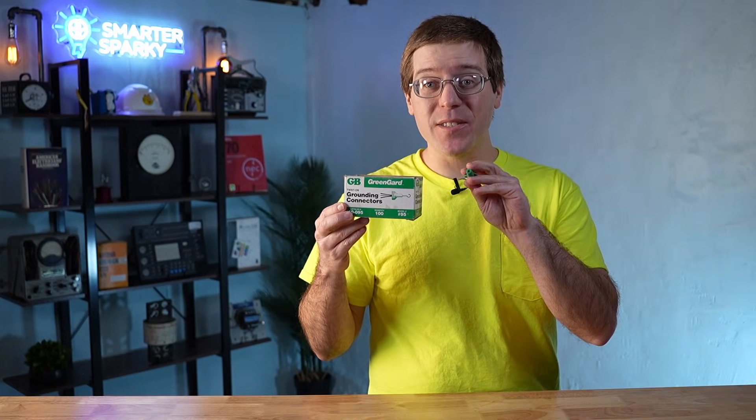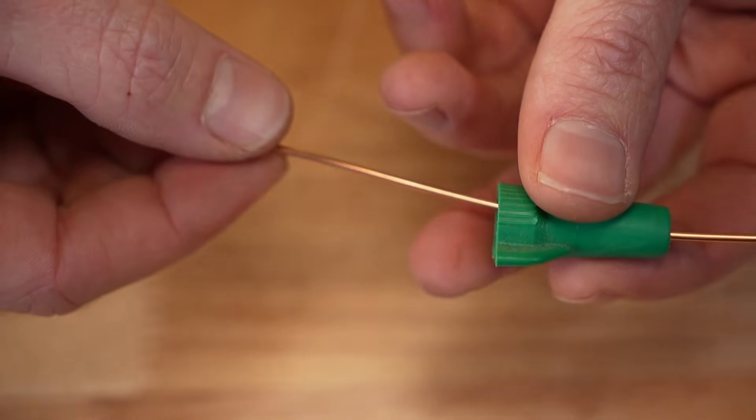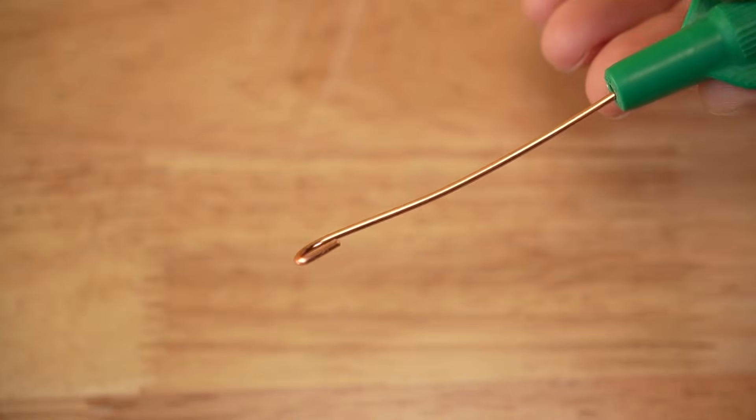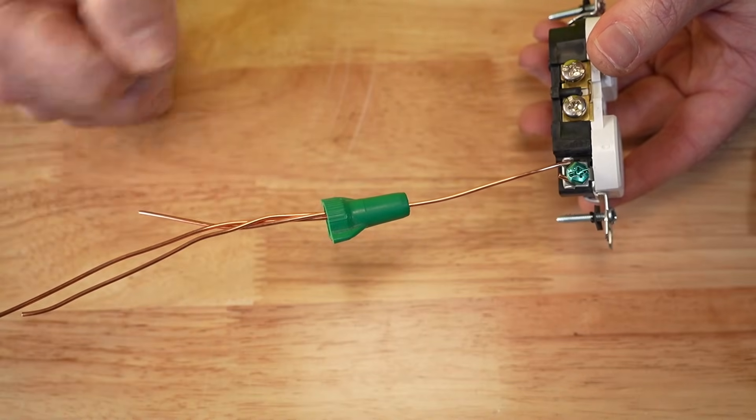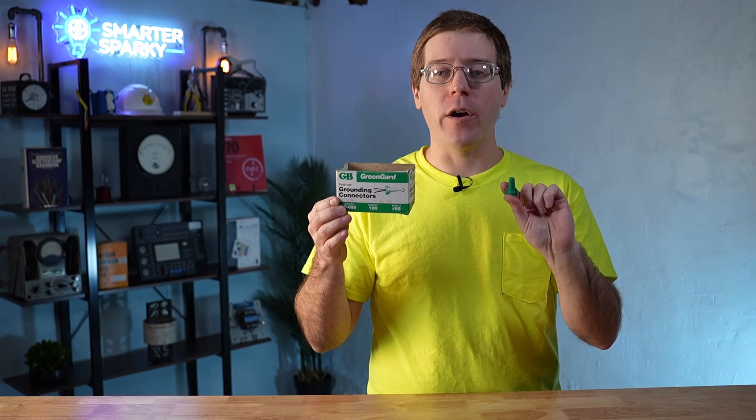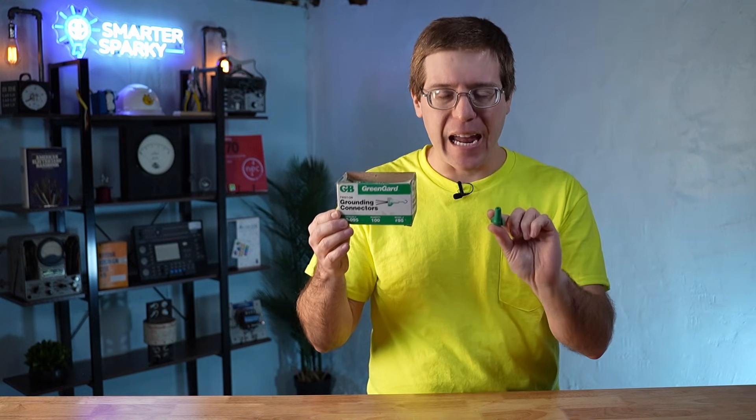They also make these green wire nuts with a hole in the top designed specifically for connecting grounding conductors like so. It's important to never use these for hot or neutral wires because the hole can leave bare conductors exposed at the top of the wire nut, creating a potential shock hazard. Use these green wire nuts only for grounding connections to stay safe and code compliant.